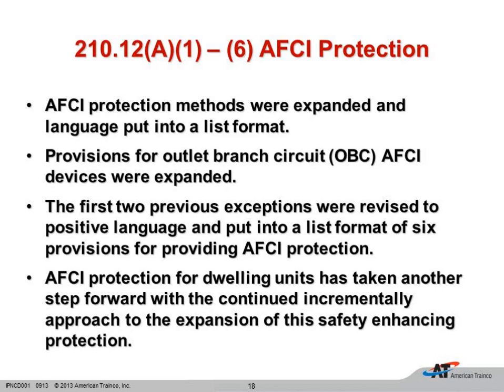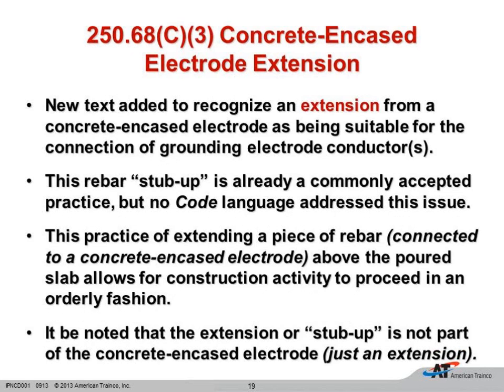Hopefully this is going to enhance the safety, cut down on the fires that we've seen, and give us a chance, I guess, to fully protect that dwelling. My feeling is that in 2017 this will also be expanded, and we'll see maybe more parts of the house. So you're probably wondering what parts of the house are not protected by an AFCI. Well, bathrooms are not in there, garages are not in there, unfinished basements are not in there. So there's a few areas of the house that are not protected by AFCIs, but we're getting close to making the whole house be AFCI protected.